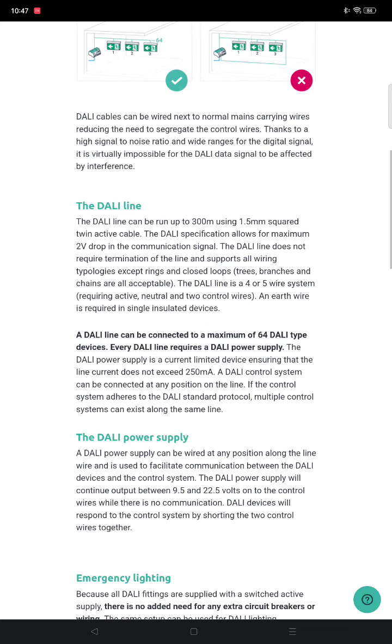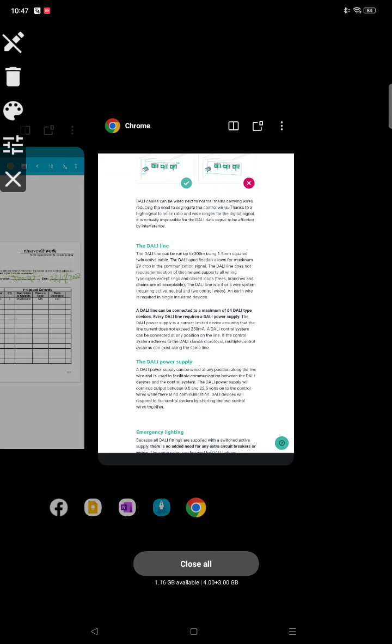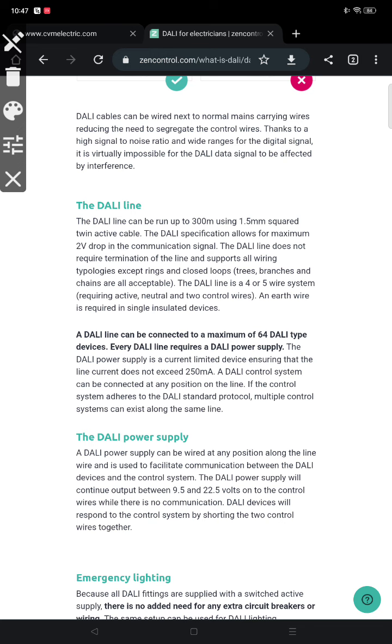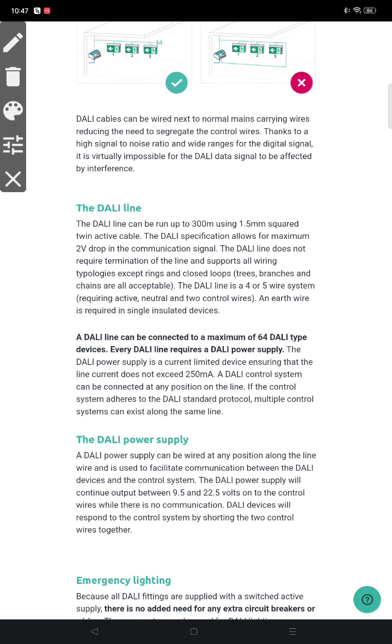The DALI line can be run up to 300 meters using 1.5 square mm twin active cable. Okay, so what I'm talking about, I need a pencil, right? Where is my pencil? So the DALI line can be run up to 300 meters, and 1.5 square mm twin, like this spiral. This is a spiral cable.